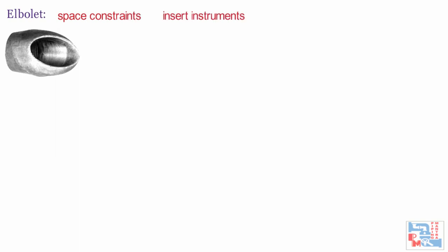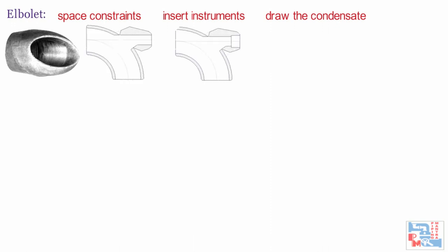Elbolet is used to have branch connections at an elbow, useful when there are space constraints. It is used to insert instruments in small-size pipes, to draw condensate from steam lines, and for temperature gauge arrangements below 3-inch pipes. It is also available in socket end and threaded end.